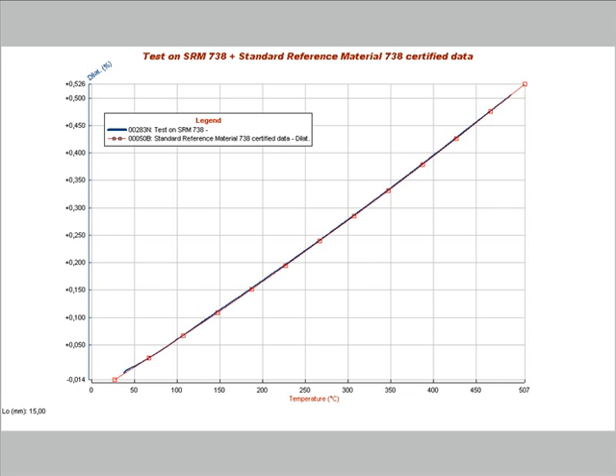For this reason, the result of the test must be corrected applying a correction curve to take in account and cancel the expansion of the measuring head. With the optical dilatometer misura LT, it is not necessary to carry out the calibration procedure, because once the magnification of the optical system is precisely defined, there is nothing interfering with the measurement.